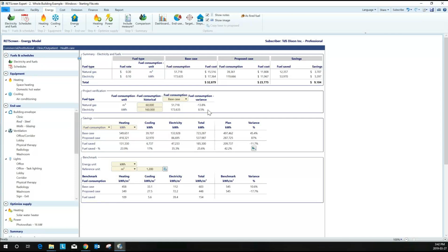Most energy audits in my world should be done this way, but I saw an energy audit report that said, assume that the building is doing this, the savings for ventilation systems will be this, and they predicted savings which were greater than the building actually consumed. Well, if you use the tools here, you'd never get into that situation, but that does happen.